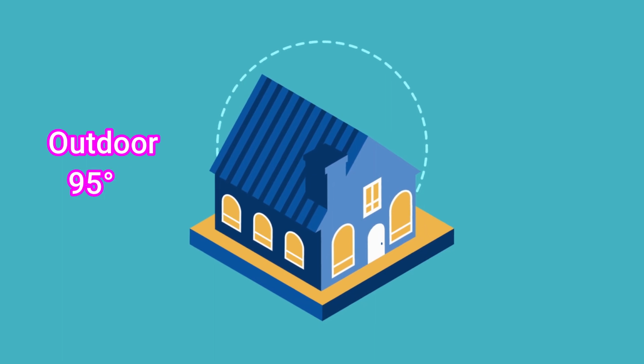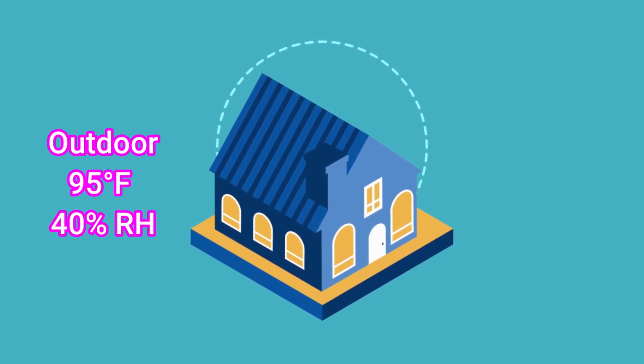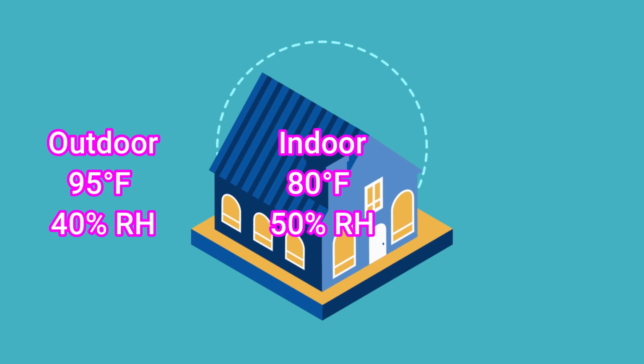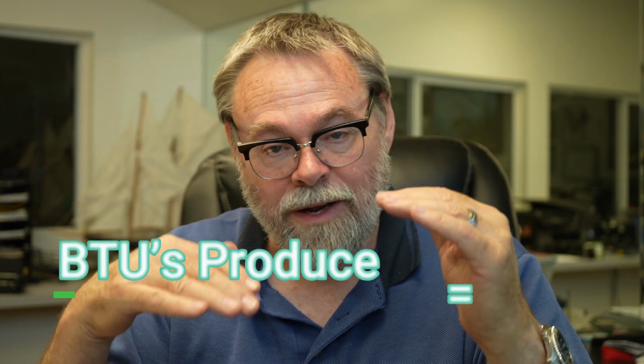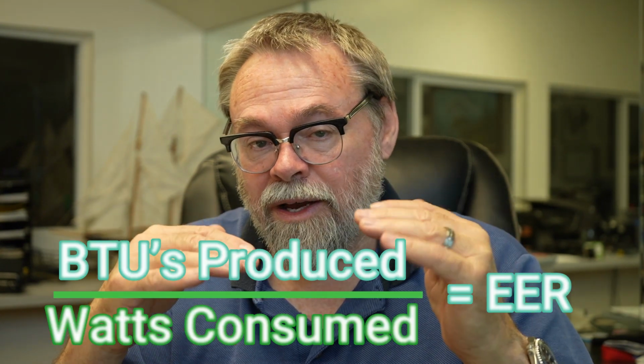I can measure EER by taking the BTUs the unit makes and dividing it by the watts it consumes to make those BTUs. Now, the way they rate a piece of equipment, whenever you hear a guy say that's a 3-ton piece of equipment, they use certain criteria to rate that at 3 tons, that it makes 3 tons of cooling at this certain criteria. The criteria being that the outdoor temperature is 95 degrees, the indoor temperature is 80 degrees, the relative humidity outside is 40%, and the relative humidity inside is 50%. They measure the BTUs the unit makes and divide it by the watts it's consuming at that criteria, and that gives them the EER of the piece of equipment.